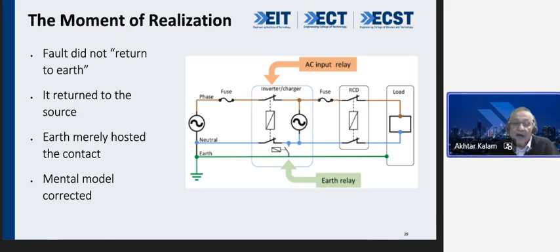So now, the moment of realization. Let me try it and realize the fault did not return to earth. It returned to the source. Earth was just hosting the contact, and the mental model had to be corrected. This is the moment that you will remember years later what I'm telling you today: that the fault does not return to the earth. It went back to the source. Earth was just the contact.